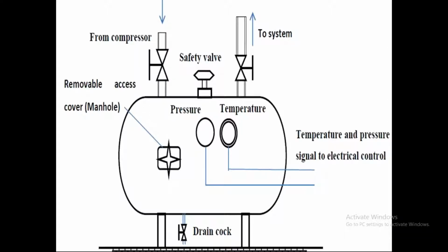What energy monitoring is needed for a compressor? This is thanks to NPTEL, the National Programme. Our government's instructions on all the equipment and all the utilities are there. Maybe you have to go into the depth of the NPTEL programs. Any air compressor needs an air receiver, but this air receiver needs a temperature and pressure signal to the electrical control panel, where it needs to give alarm and shutdown condition.